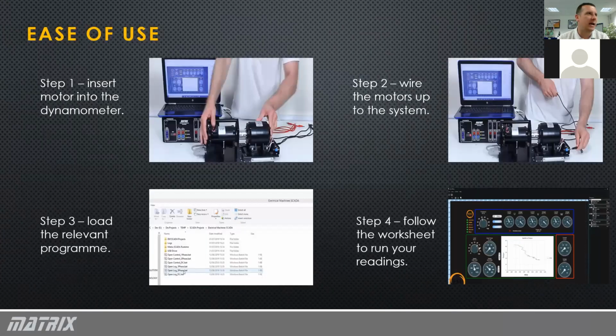The system works, as you can see on screen here, using the control box, which can either be connected to a PC if you're using the PC software, or used manually. The user inserts the machine into the dynamometer, wires up the motor or machine into the system, loads the relevant software program if applicable, and then follows the worksheets available in order to take readings and conduct measurements.